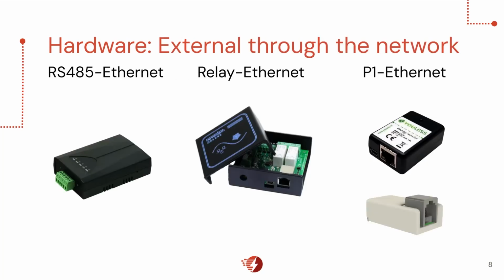Now, for the external hardware I talked about, we have a few options here. We have an RS485 to Ethernet connection, as well as the relay, as well as the P1 to Ethernet connection. These are mainly for assets which cannot be hooked up directly to our controller. If we have, for example, an inverter that only communicates through Modbus RTU, so we need the RS485 connection, but the controller is too far from the inverter, then we could use one of these extenders to put them through the network. Do keep in mind that they have a different protocol. So when adding the asset, you would have to choose the specific protocol, but I will come back to this with an example later.